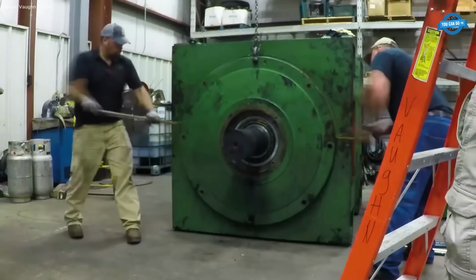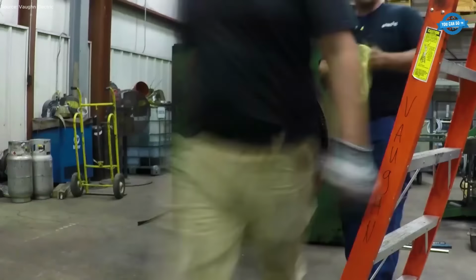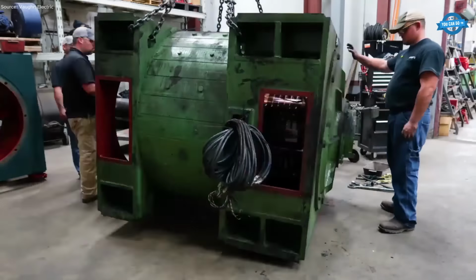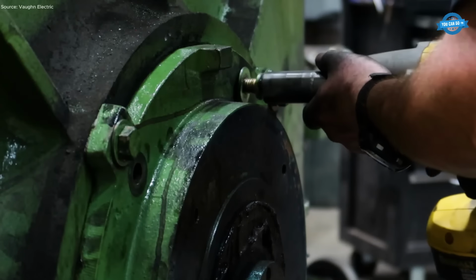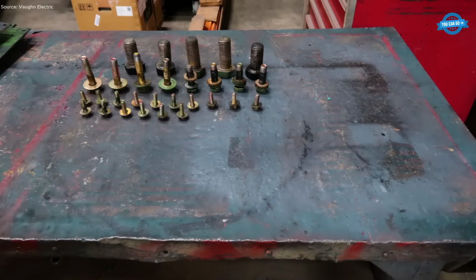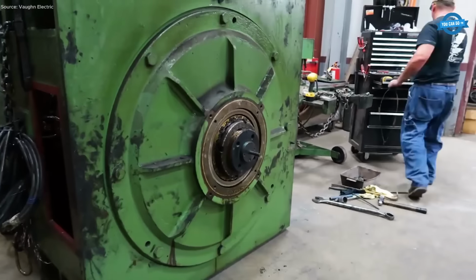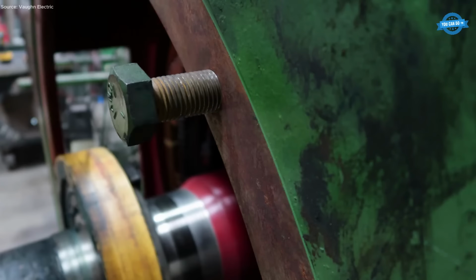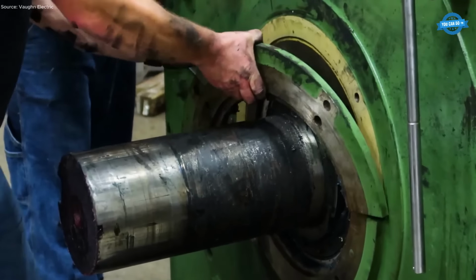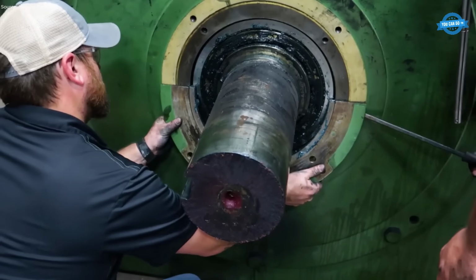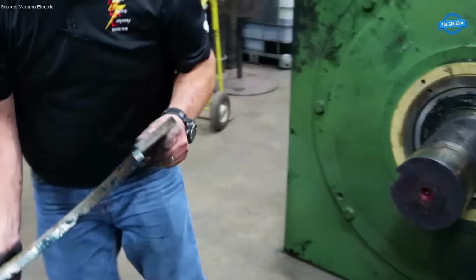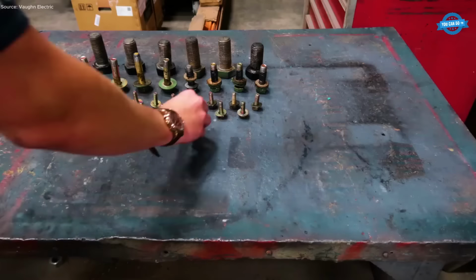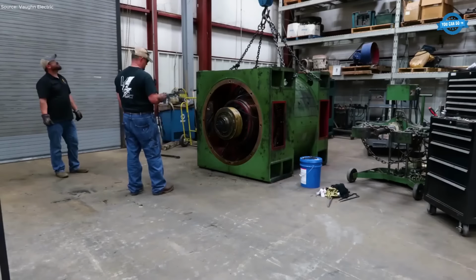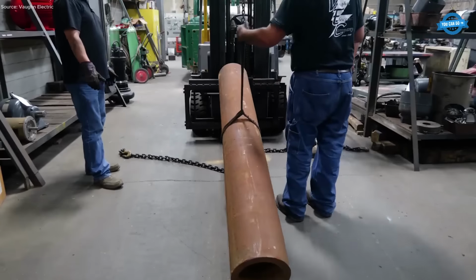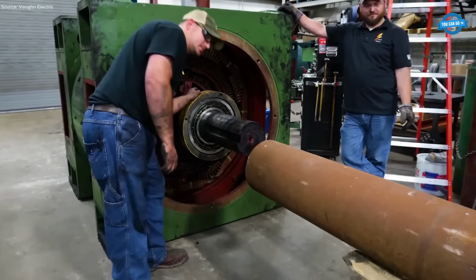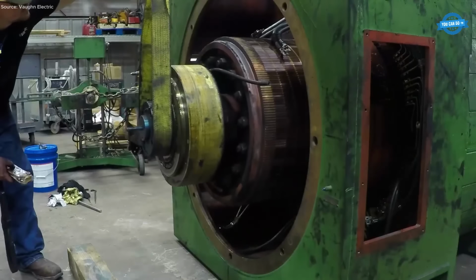The first step involves the careful disassembly and inspection of the motor. Technicians methodically take apart the motor to evaluate critical components such as the stator, rotor, bearings, and windings. By conducting detailed measurements, they identify any signs of wear, damage, or degradation. This thorough assessment forms the foundation of a tailored repair plan, ensuring that all issues are addressed to restore the motor's functionality. The precision of this initial step sets the stage for the subsequent phases of the overhaul.